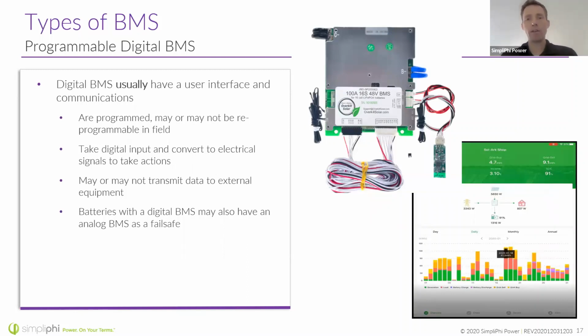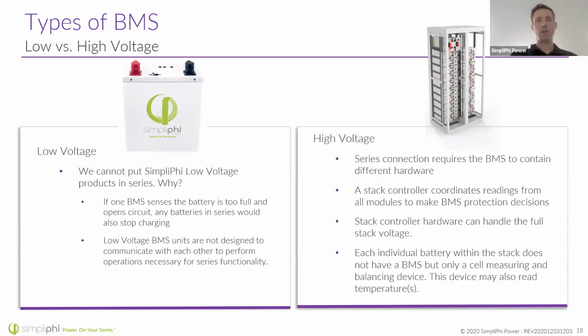Here's an example of a BMS you can buy online, I think from overkillsolar.com. I bought one of these a year or two ago. This is a 16S, meaning 16 sets of cells in series to produce 48 volts for LFP. These are programmable, and may or may not be programmable in the field. This one has a Bluetooth dongle hanging off the side, temperature sensors here that could be integrated into the battery, and balancing wires on the bottom. Your connections to the battery and cells are here. This one allows you to transmit data, it's a digital BMS, and it gives you an output so you can see how your battery is behaving over time.